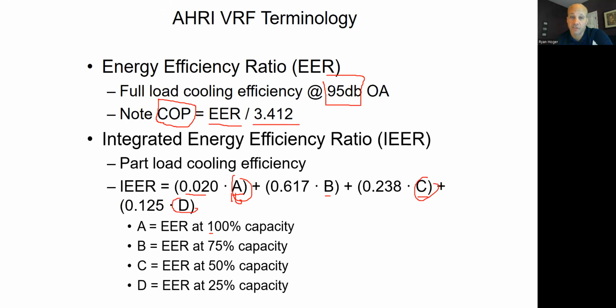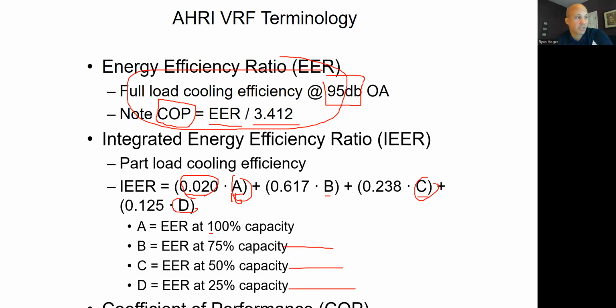So we take that average, we take this EER, this little EER right here, and we say that only happens 2% of the year. So we'll count that 2% of the time. And then we're going to rate this guy 62% of the time, 24% of the time, and 12% of the time, and then average all that out to get the IEER. That's for cooling. And then for heating, we'll look at COP on the bottom. That says COP, coefficient of performance we have for heating.